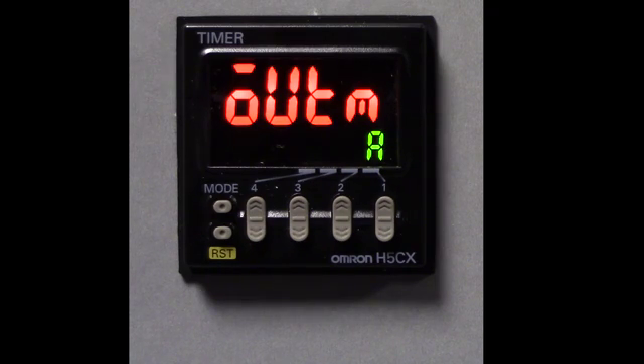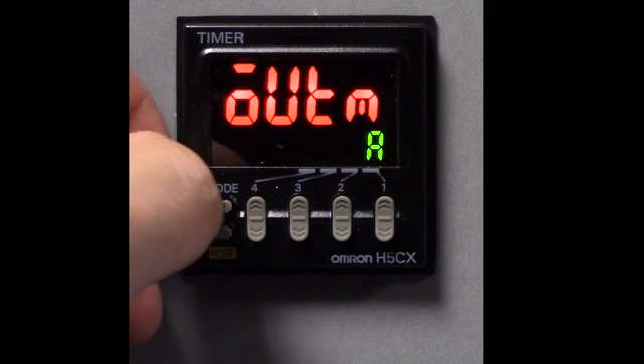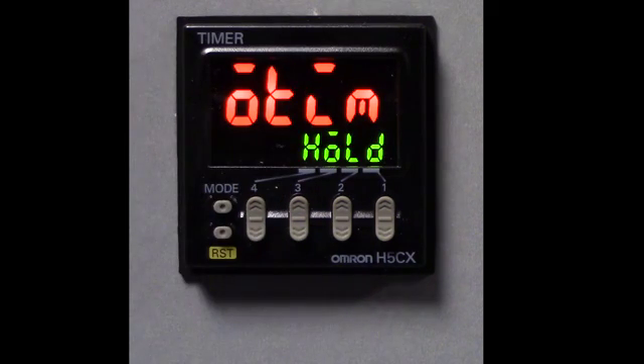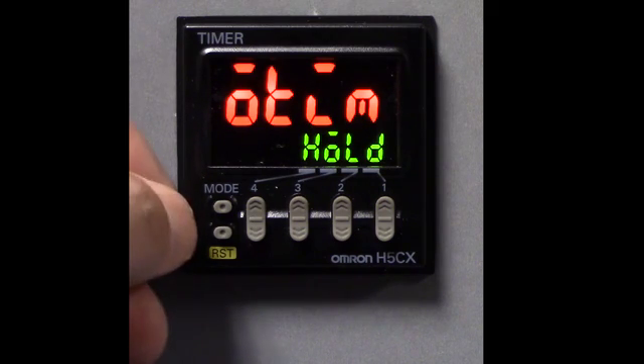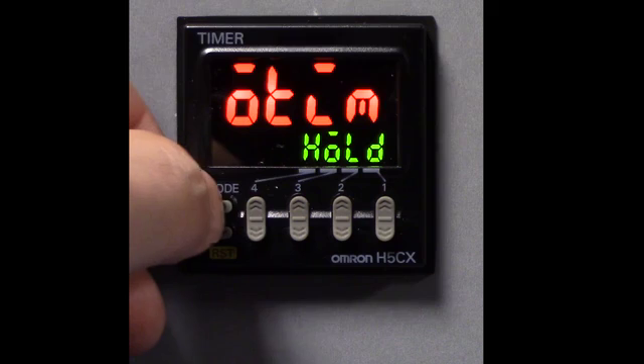So now I'm going to press the MODE key. We're going to have the next function, OTIM, and this has to do with the functionality of the contact transfer, and the factory default is hold. So what happens is when the contacts transfer after the timing sequence, they will then hold. So I'm going to use the factory default.